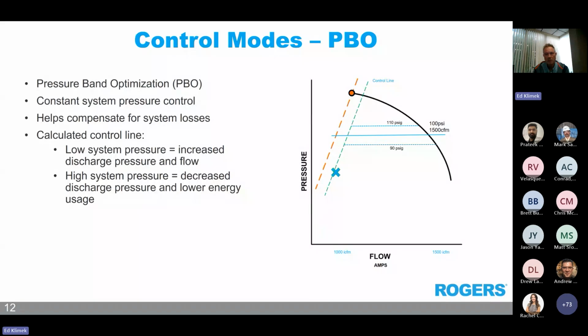So as the compressor loads to its minimum operating point, as the downstream system pressure changes, the operating point will dynamically change through the PID controller within the pressure band. And it maintains that constant downstream system pressure, as you just saw.